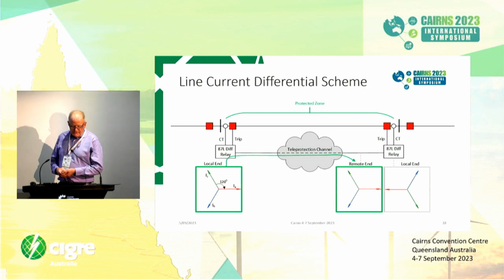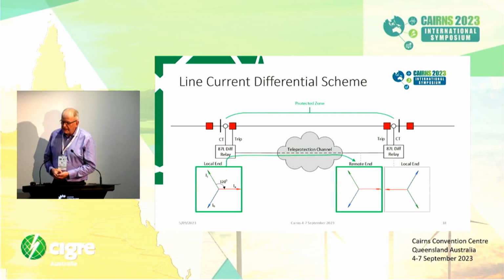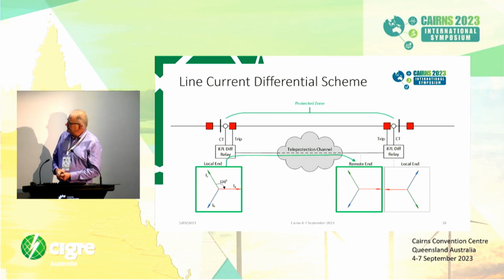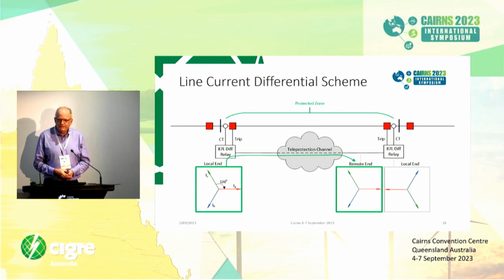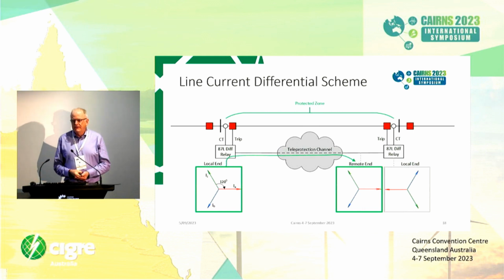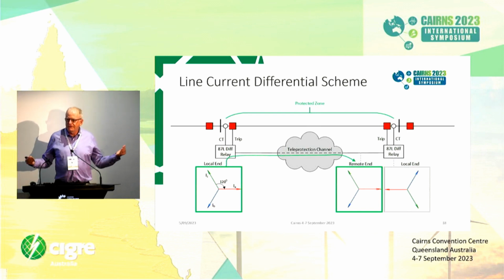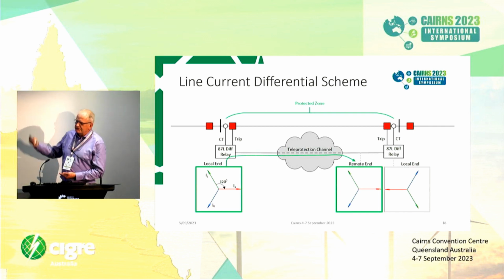So it's quite critical that your teleprotection channel has deterministic latency so that the angles of the vectors at the local end match the remote end. And you can see there that both of those three-phase vector diagrams are in sync, okay? So the way the scheme works at the remote end, the protection relay compares the remote end current vectors with the local end, does a vector sum addition, and if the vectors sum to 0, that means that current flowing in the line at one end and out of the line at the other end are in sync, so there's no spill current or no fault on the transmission line, so it's all good.